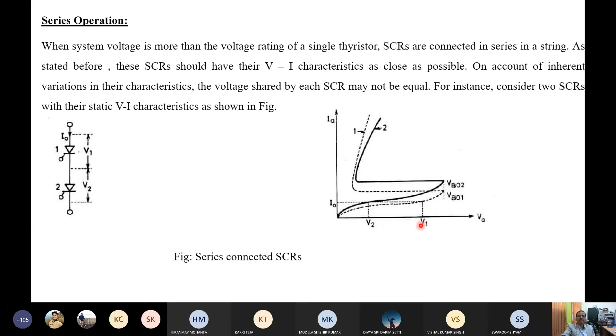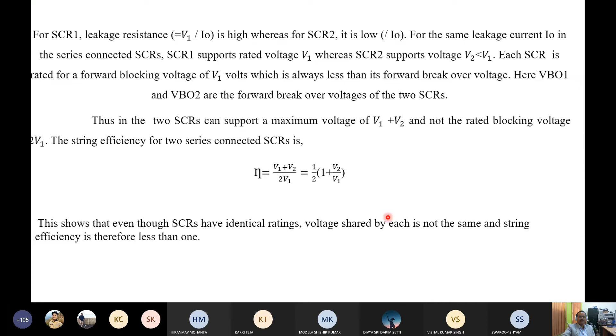We'll choose the worst case. Leakage current, you just tell me which thyristor has leakage current. This one. This is during the off period, right? This is the conduction current. This solid line has larger leakage current, and the dotted line has less leakage current. So the thyristor having less leakage current is supporting the maximum voltage V1, right? This is already explained, why the string efficiency is less than 1.